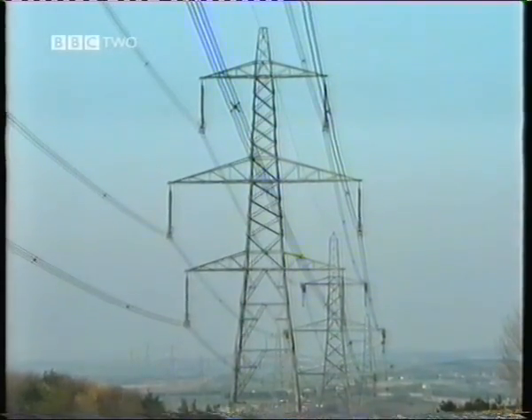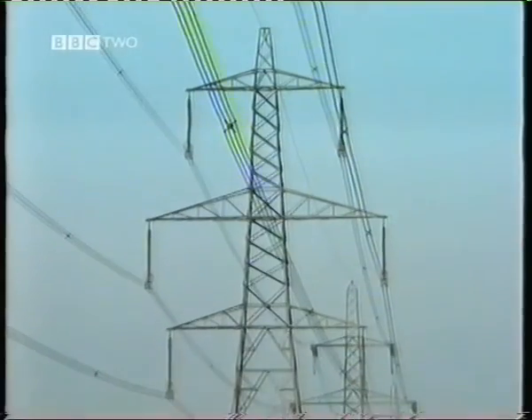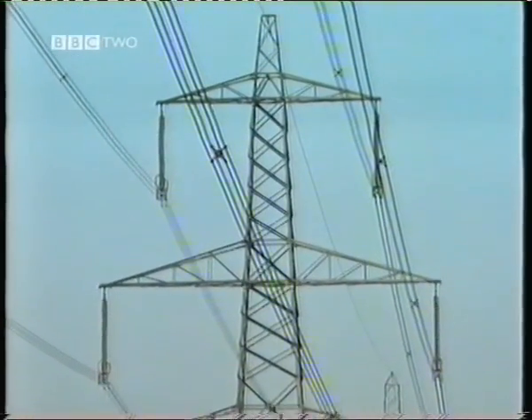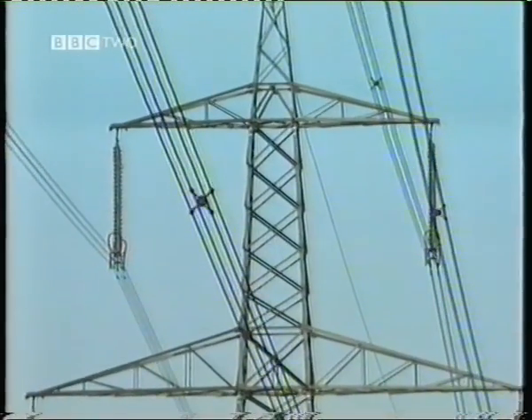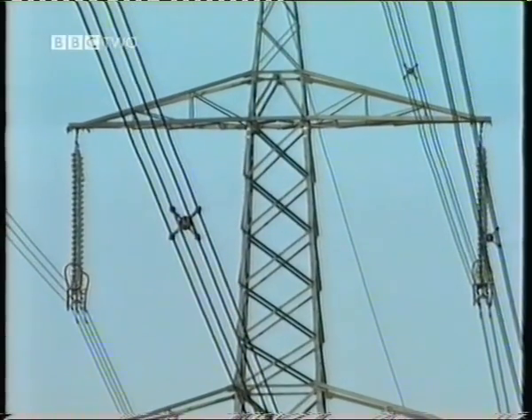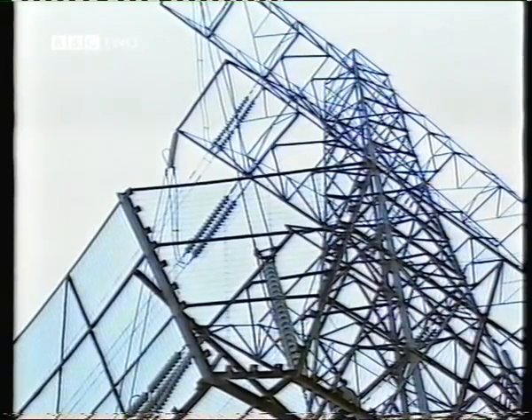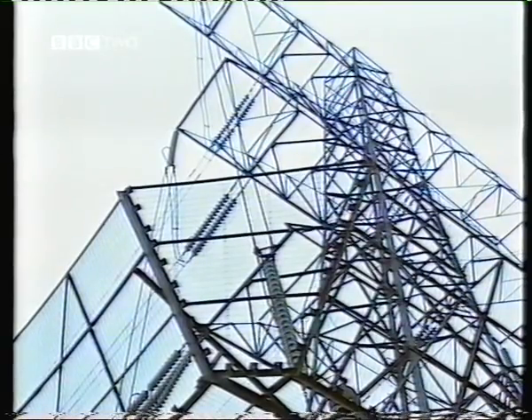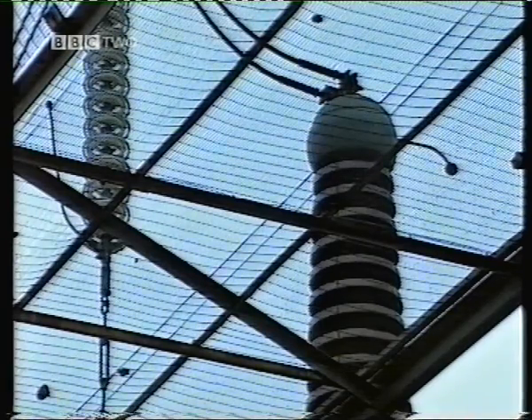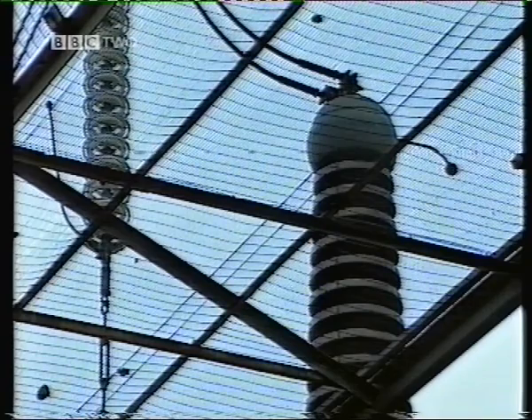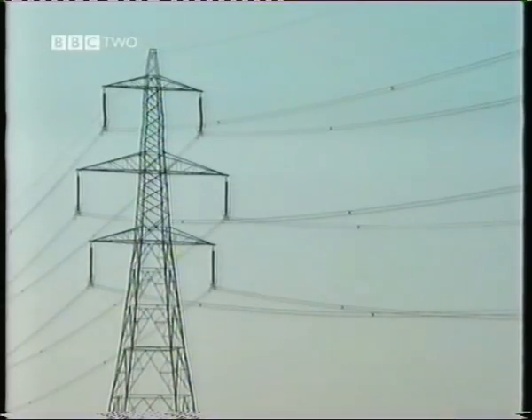Of course, the weight and tension of the line must be supported by load-bearing connections between the lines and the pylon, and at 400 kV, the conductor must be no closer than 1 metre to the tower, or even the ground when it comes down to a substation. The loads may appear to be lighter here, but some of these insulators contain high-pressure gas. What's needed is an insulating material strong enough to hold its own weight and that of the cable and extra loads from wind and ice. What material would you use?